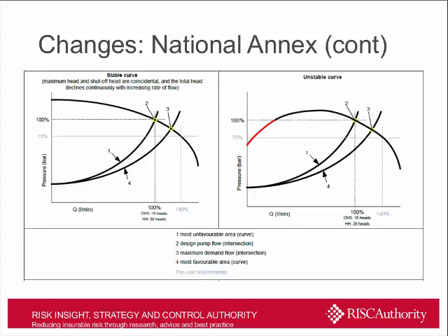So, a stable pump curve with a steady declining head is essential for the calculation principles of both BS EN 12845 and the LPC rules. However, the latest CEN publication has done away with this requirement, which used to be stated at Clause 10.